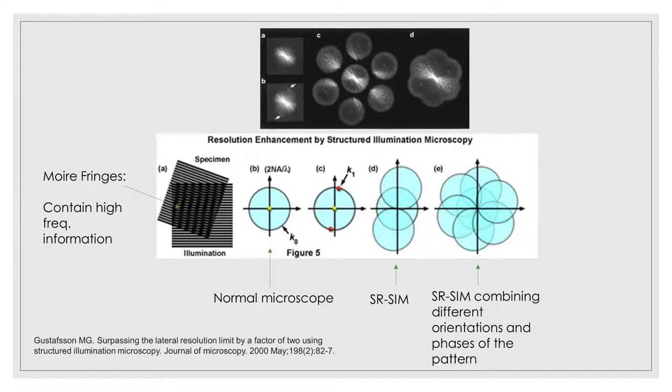To obtain all of this information, we need to take a series of images with the pattern at different phases and different angles. And this results in seven sets of components, as you can see in the image. These will then be computationally separated and recombined at their proper positions. And since the new reconstruction contains information from twice as far out, it's able to double the resolution. After reconstruction, the data is inverse Fourier transformed to produce the super-resolution image.